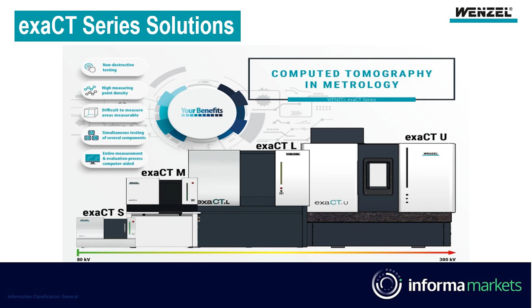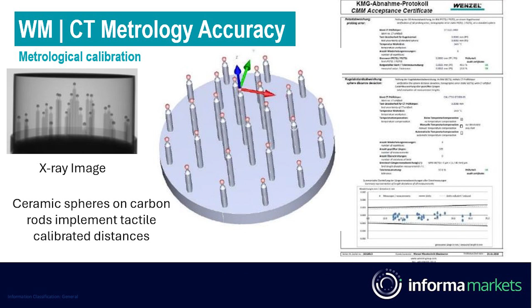As I said, we calibrate each machine using what we call a birthday cake. It is ruby balls on studs that are exactly calibrated. We then provide a certificate for the whole calibration throughout the range of the CT scanner's capabilities. And it's repeatable too. This is very important, especially with metrology devices, that you can run it all day. Make sure you maintain the temperature. The granite provides stability throughout the range, and we're able to repeat our measurements for months.